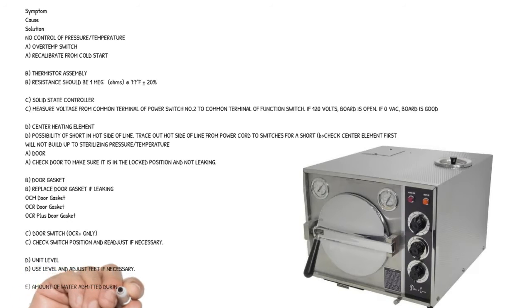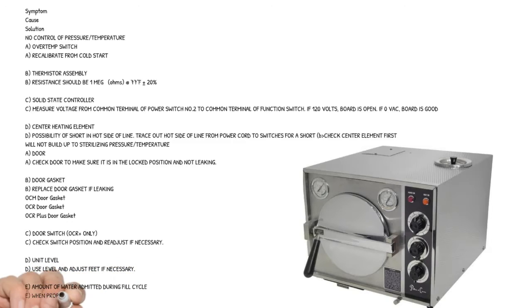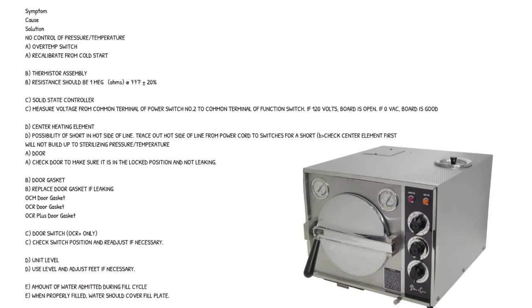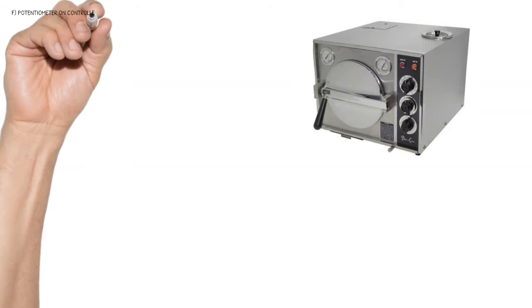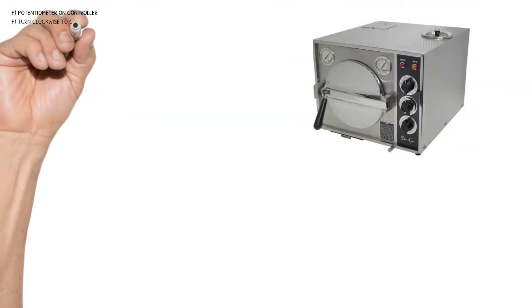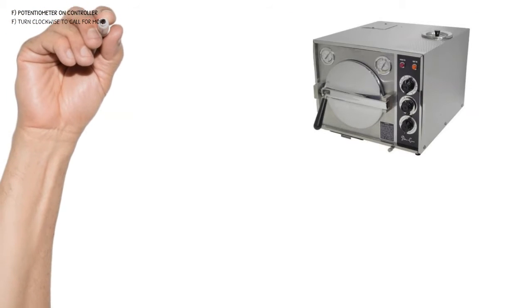Cause E: amount of water admitted during fill cycle. When properly filled, water should cover fill plate. Cause F: potentiometer on controller - turn clockwise to call for more heat.